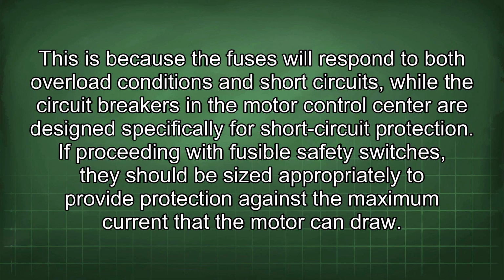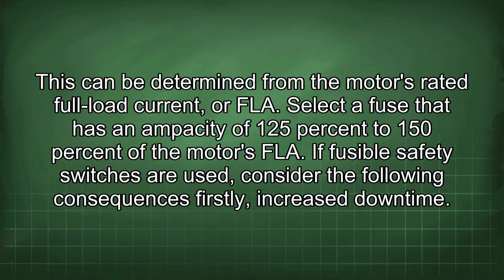If proceeding with fusible safety switches, they should be sized appropriately to provide protection against the maximum current that the motor can draw. This can be determined from the motor's rated full load current, or FLA. Select a fuse that has an ampacity of 125% to 150% of the motor's FLA. If fusible safety switches are used, consider the following consequences.